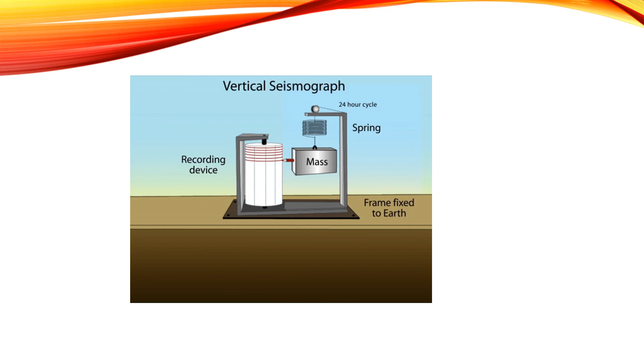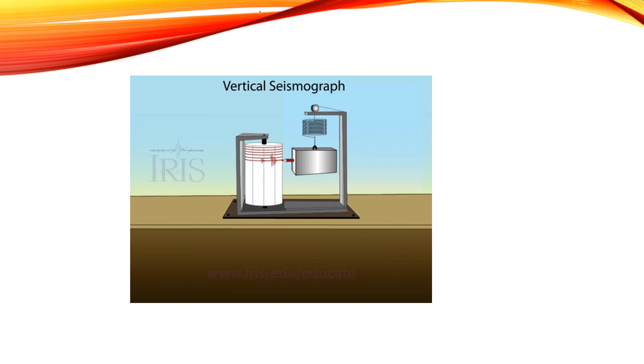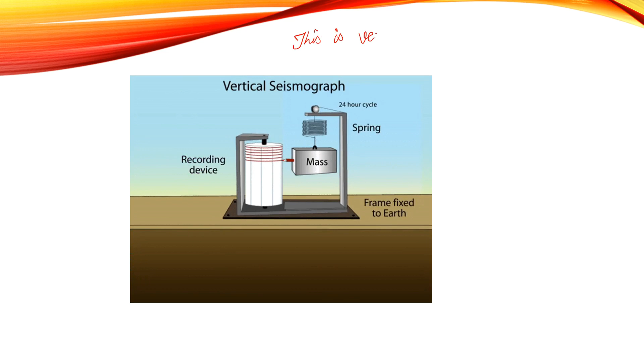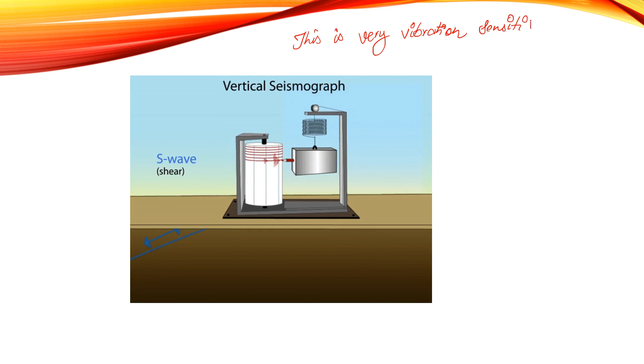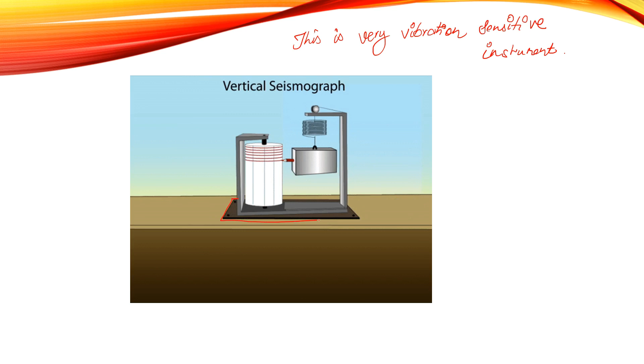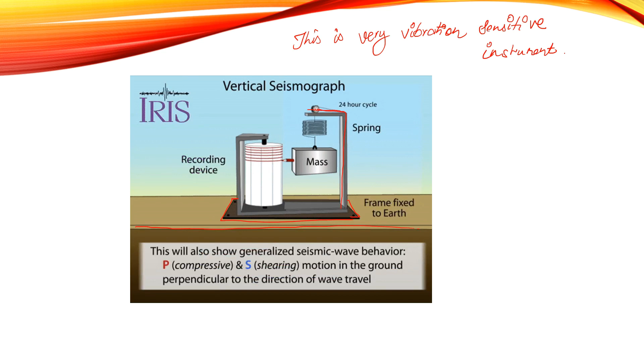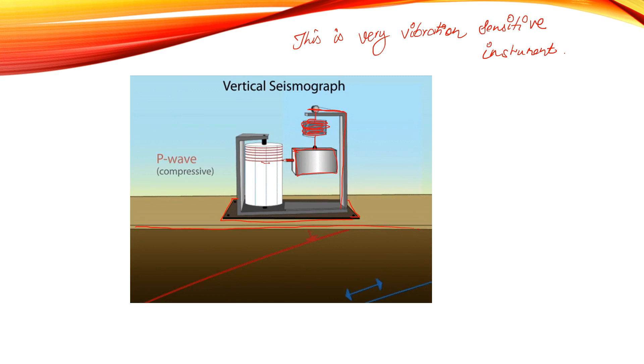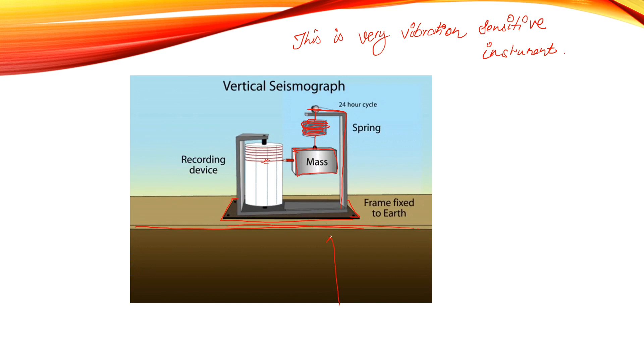This is the whole set of the seismometer instrument, which is used to record the vibration from the earthquake. This is a very vibration-sensitive instrument. Here, this is the base of the seismometer, which is fixed to the earth's surface, and this is the frame of the seismometer. The frame is attached to a spring, and the spring is attached to a heavy mass, and the mass has a pen which is used to draw the record of the motion of the ground. When the surface is hit by the seismic wave, the base of this instrument vibrates and records the seismic wave.